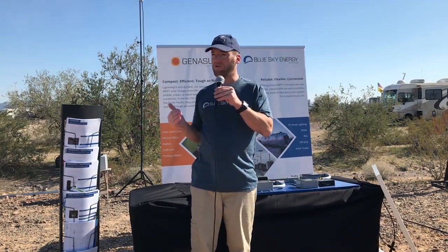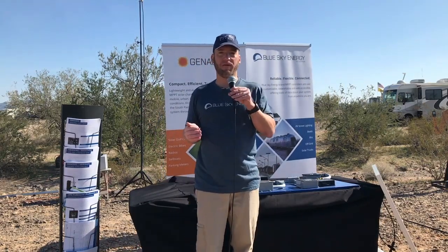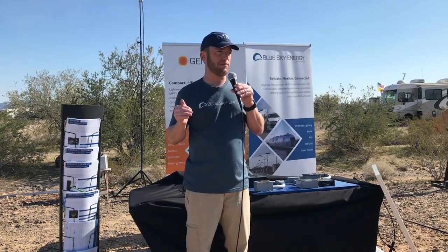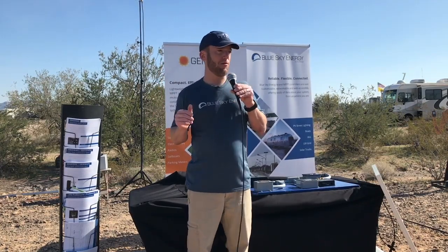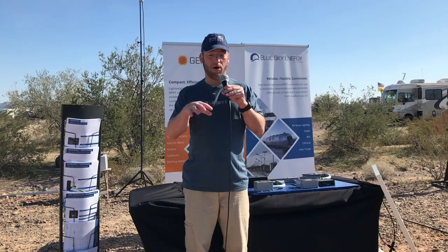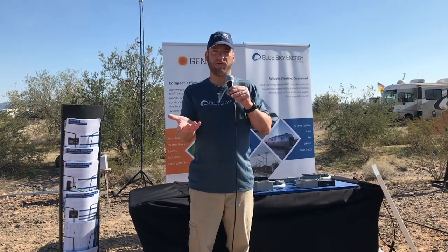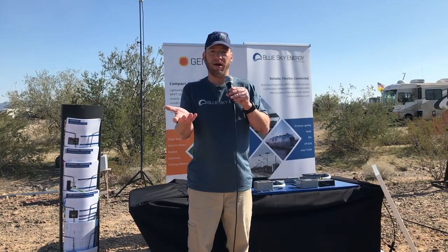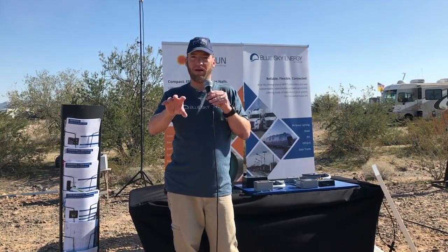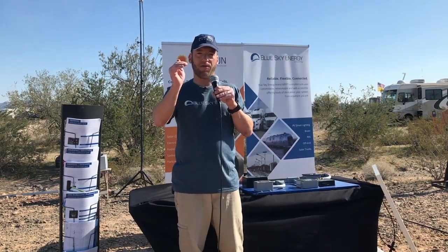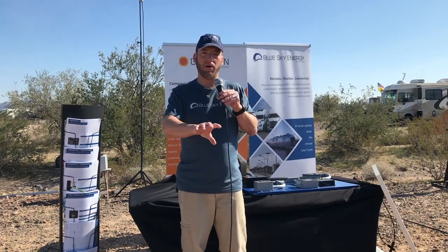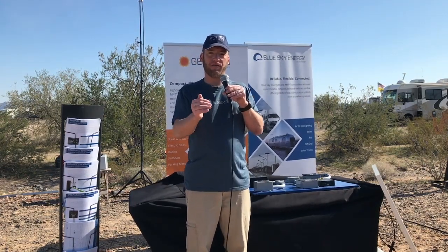Now, if you have multiple charge sources, basically the highest voltage wins. Let's say your Magnum inverter is floating at 13.1 volts, and your controller wakes up in the morning. When it first wakes up, both the controller and the Magnum are going to try 100% to raise the battery's voltage to 13.1. Once the battery gets to 13.2, the Magnum inverter has 0 amps output because it's just trying to maintain 13.1 - if the voltage is higher than 13.1, it turns down its output; lower, it turns up its output. It's providing constant voltage at a set point.